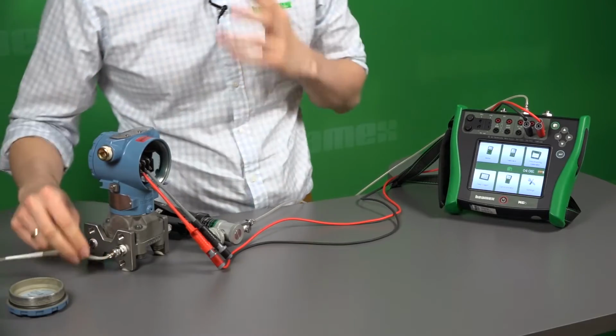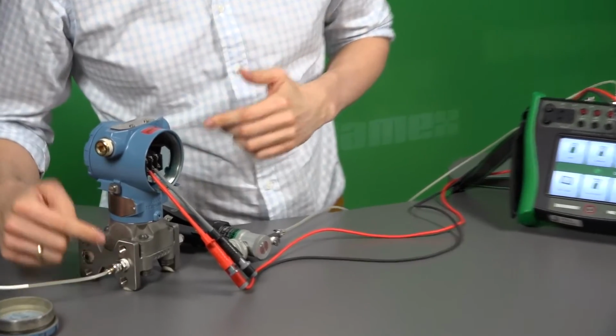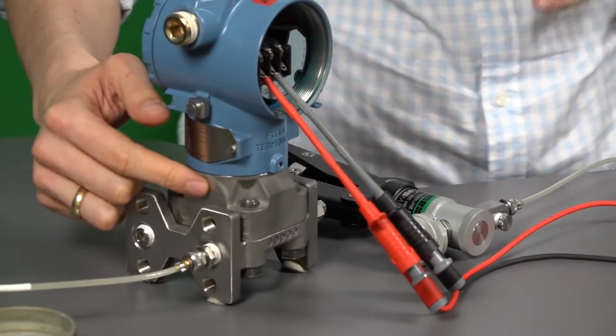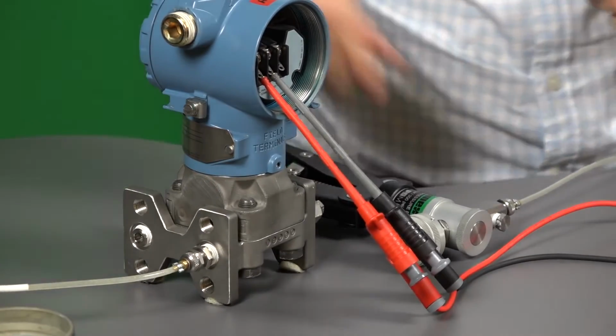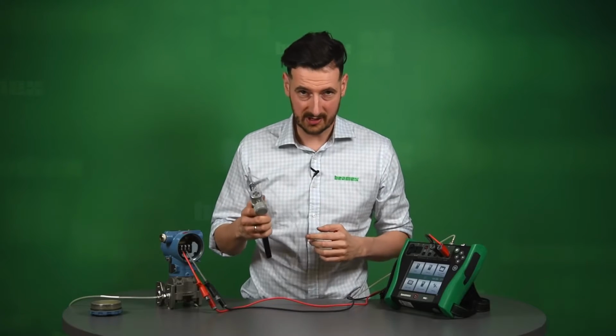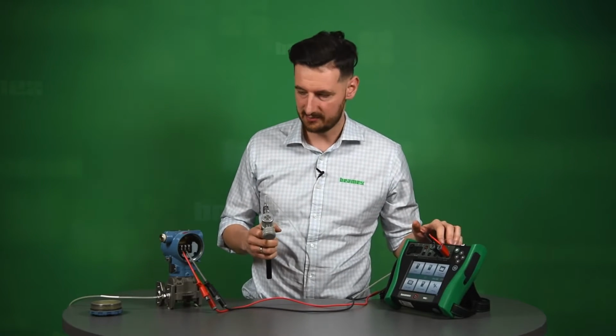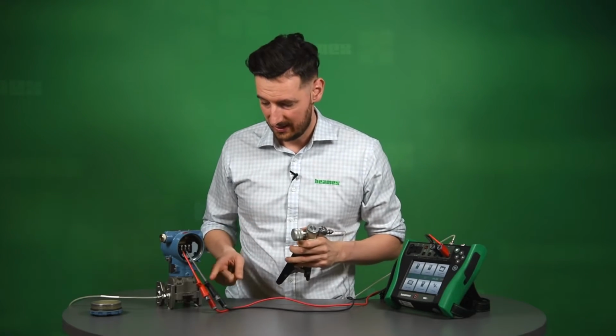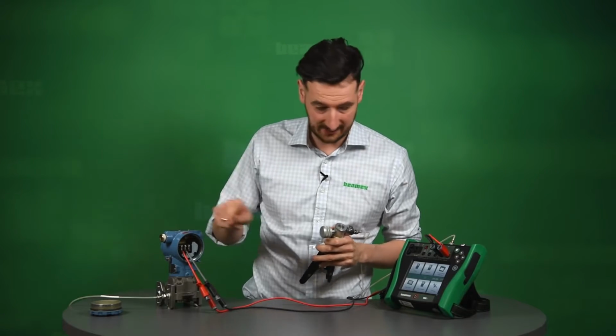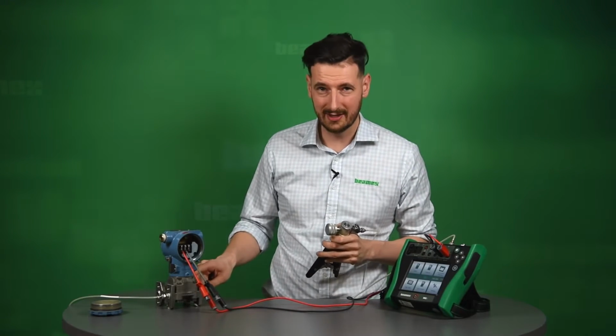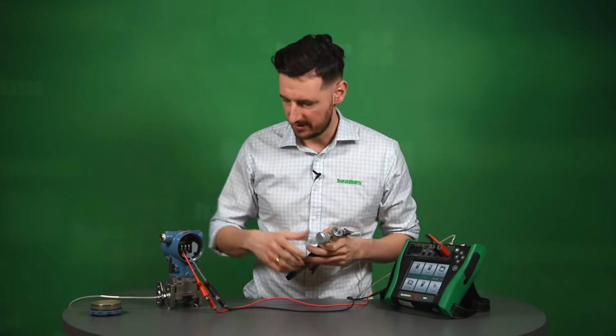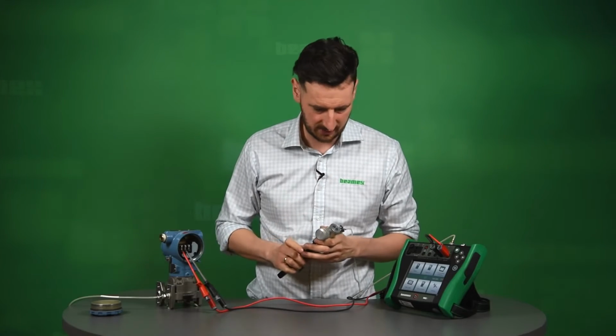You can see also that the connection is made to the high leg of this differential pressure. Basically the high leg is going to go to a pressure source and also the calibrator. So we're going to pressurize that to get the milliamps response. Also the low leg is open to atmosphere. So we've got all that set up right now.